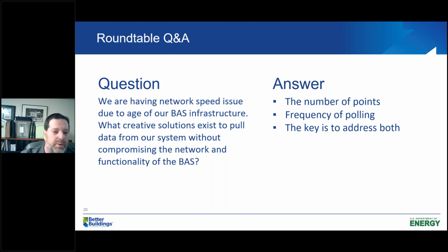So don't let slower networks prevent you from implementing a successful EMIS. As a general rule of thumb, for legacy systems, 15 minutes or even longer, or rotations if needed. For newer, more robust BAS infrastructure, 1 to 5 minutes—though 1 minute typically isn't needed. It shows more oscillation, but there's a tremendous amount of information that can bog things down, so I'd use that less frequently. 5 minutes should give you enough information.